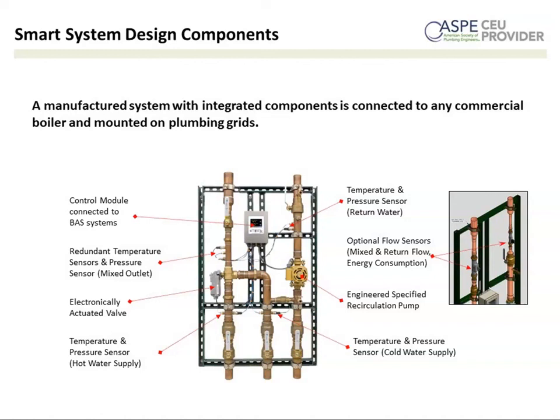So there's a question that says, what pressure drop would be expected on average with this type of arrangement? I would say what we see most people working with engineers specifying around is a 5 to 10 psi pressure drop. That's most common. Very little above 20. It seems to be in that 5 to 10 psi range right now. And this is a good reason to take a closer look at some of the online tools that are available that can help calculate pressure drop and properly size valves. And I'll touch on that in just a little bit.